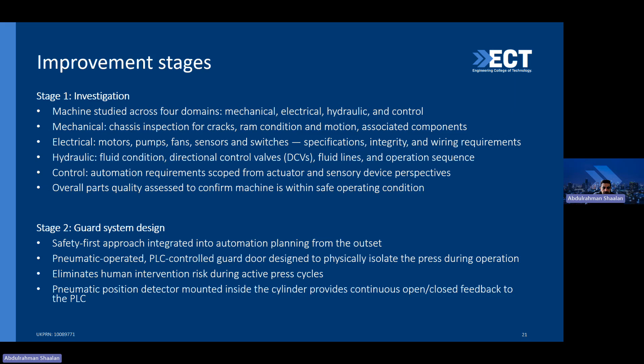We identified a pneumatic position detector that is mounted inside the cylinders to tell us where that door is. So if it is open, a pneumatic cylinder typically looks something like this. It's just a cylinder that extends and retracts. Typically we'll have a sensor here and a sensor here, and these two sensors will detect if it is extended or retracted. Because towards the end of that cylinder's extension and retraction, you have a metal plate, and that metal plate can be detected by a basic proxy sensor.